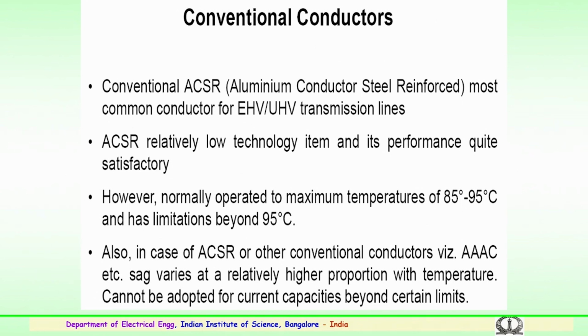The conventional ACSR, that is aluminum conductor steel reinforced, which we discussed in the earlier lecture, is the most common conductor used for EHV, that is extra high voltage, and ultra high voltage transmission lines. We know that ACSR is a relatively low technology and its performance is quite satisfactory, and it has been used for several decades both in the country and in many other countries.